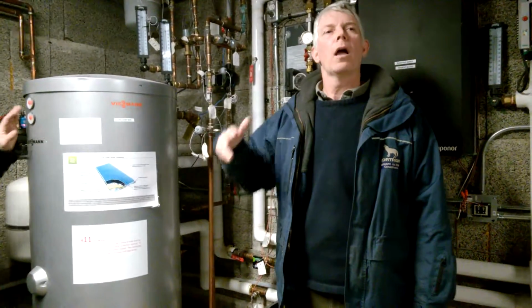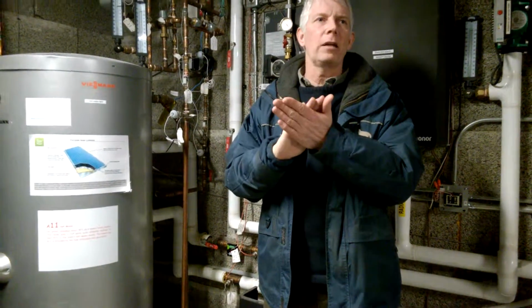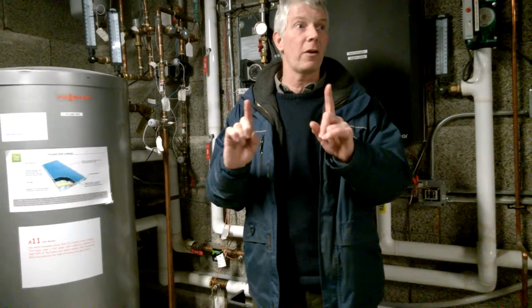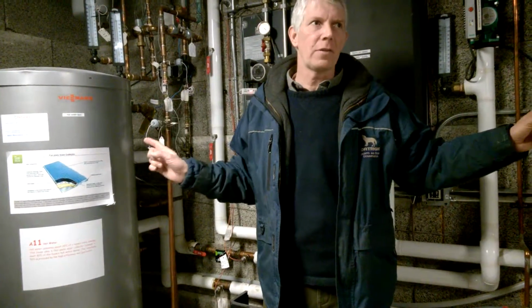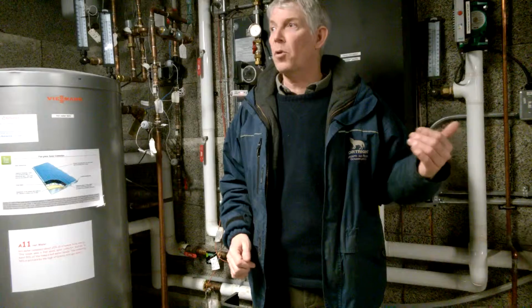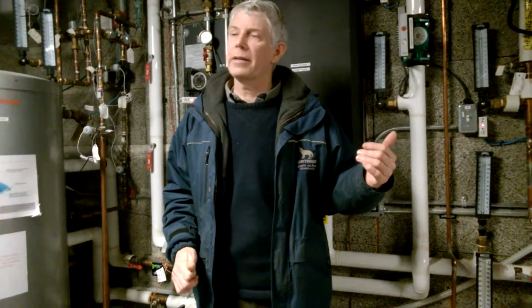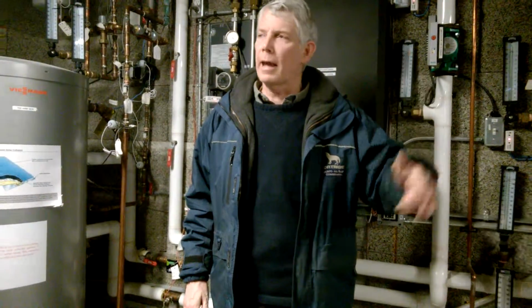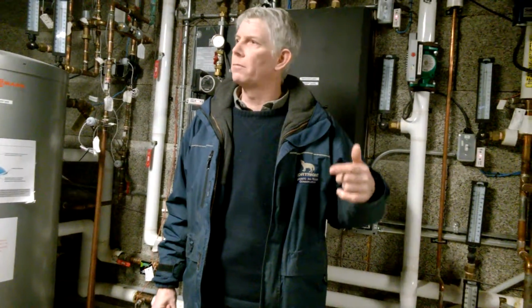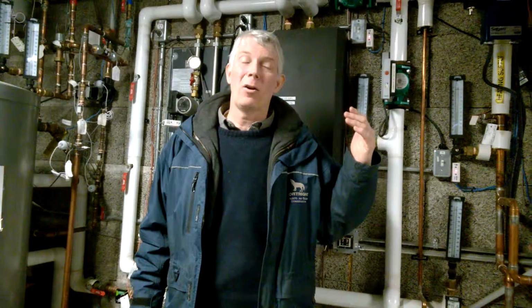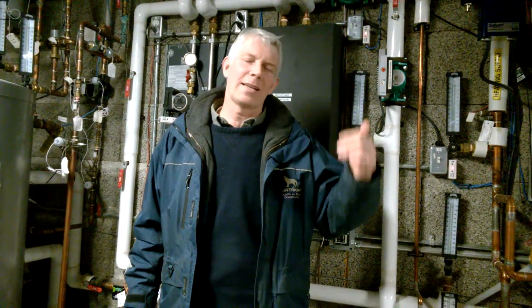At this end, you've got hot water on one side of the coil and water on the other. You don't have that really hot surface for the calcification. So therefore, the energy efficiency of the system remains high. Whereas if you put on-demand hot water heaters in, you're into a cycle of running chemicals through it to clean out the calcium over and over again. And up at my camp in the summer, it only went for 7 years, and then the chemicals ate the heat exchanger. So it's better to have a hydronic cycle.